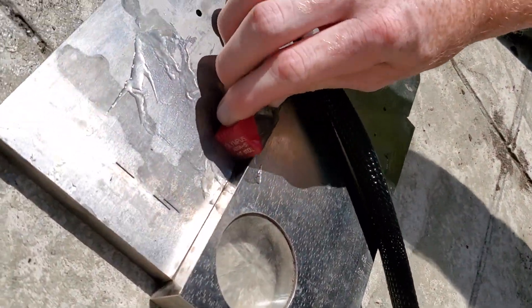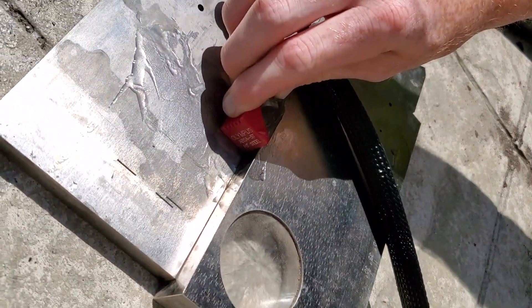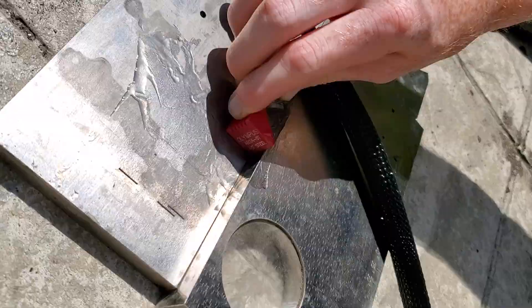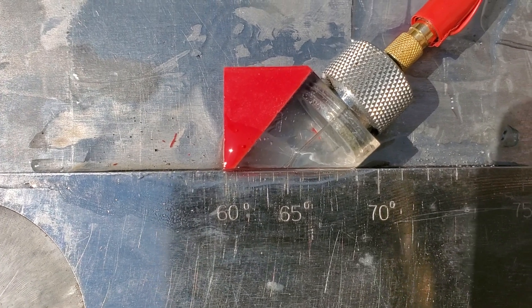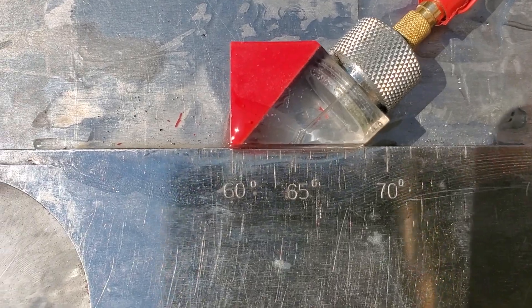We're going to move the transducer back and forth, hit the nice big circle in the IIW block, peak that signal right in the middle, and we're going to find that we've got an angle of about 64 degrees.